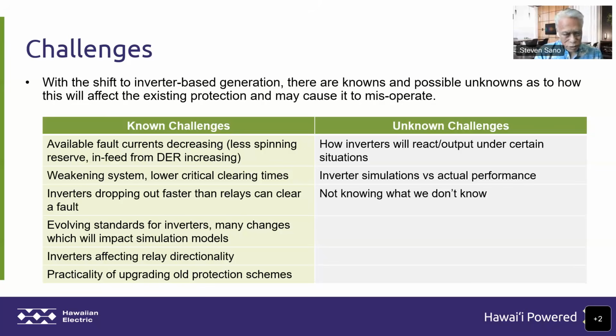Many evolving standards for inverters. For those of you following 1547 and the other transmission standard that escapes my mind at the moment, our standards are constantly evolving. Inverters can affect relay directionality. This is a real concern for anyone in the protection field. And then the practicality of upgrading old protection schemes. It's just very challenging to change some of the old stuff that we have. So that's sort of the known challenges. Unknown challenges: how inverters will react or what their output will be under certain situations.